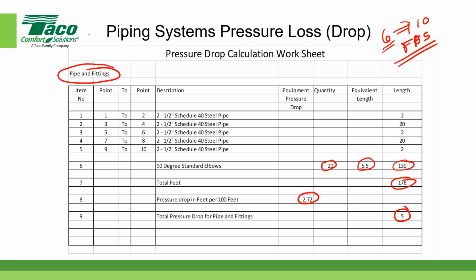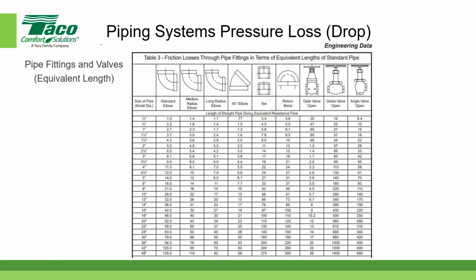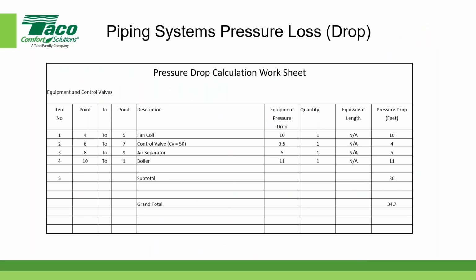Yep. So the first category, again, was pipe and fittings. Now let's go to the next category and talk about equipment and control valves. So here's the one that always catches everybody. So if you'll notice, remember from point 4 to point 5, I had a fan coil in there, and the pressure drop for the fan coil is 10 feet.